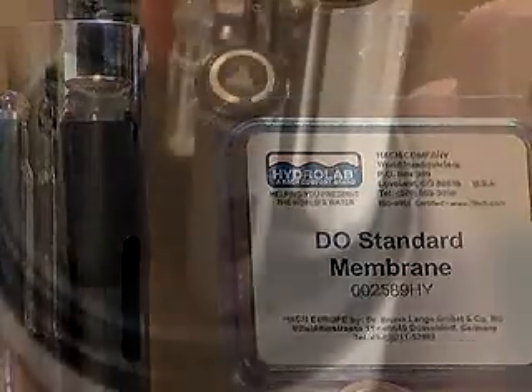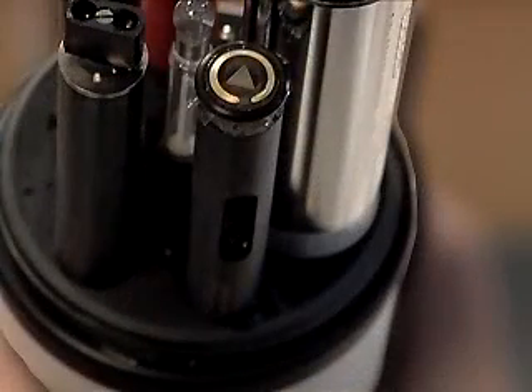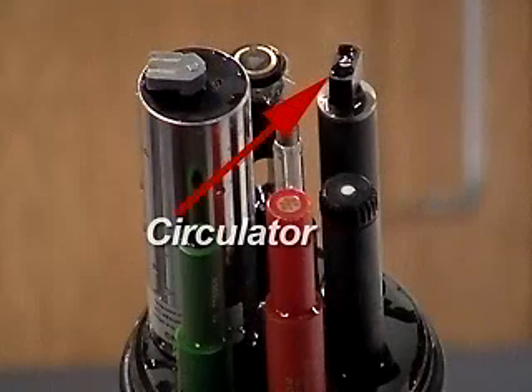oxygen-permeable membrane. As oxygen crosses the membrane, it is consumed in a chemical reaction which generates a small electrical current between the electrodes. The current measured is directly proportional to the amount of oxygen in the water sample. Since the oxygen is consumed from the water surrounding the sensor, the water must be replaced either by natural flow or the use of a circulator to prevent the readings from drifting downwards.